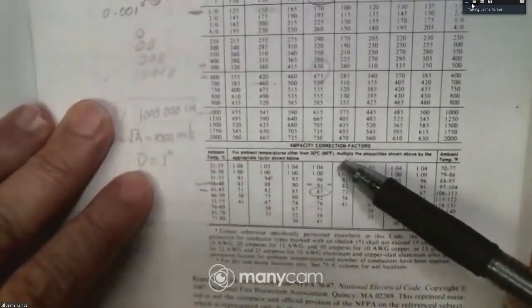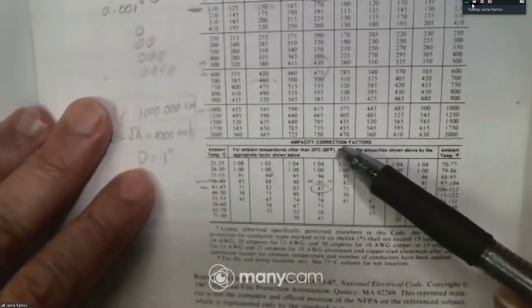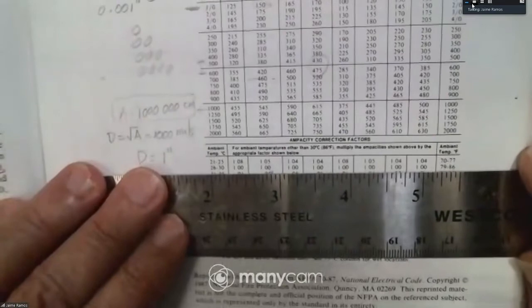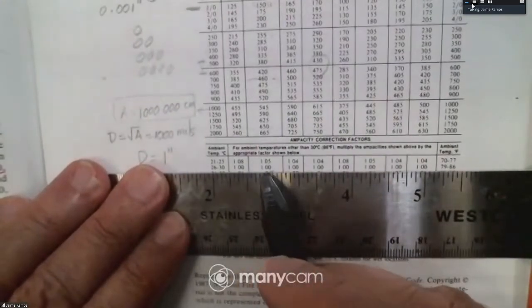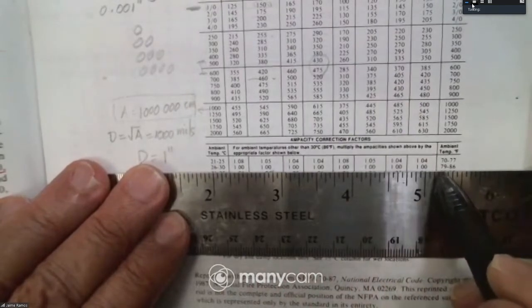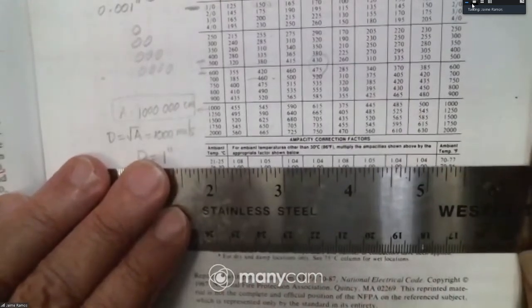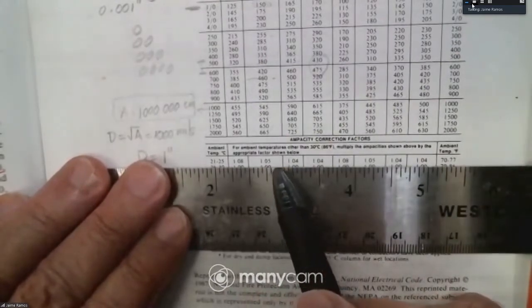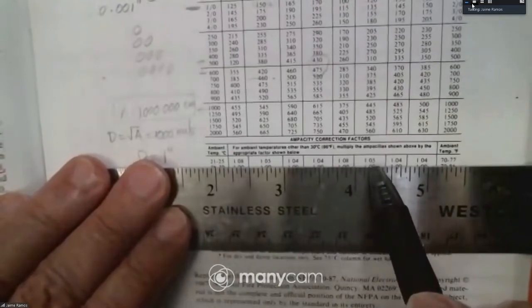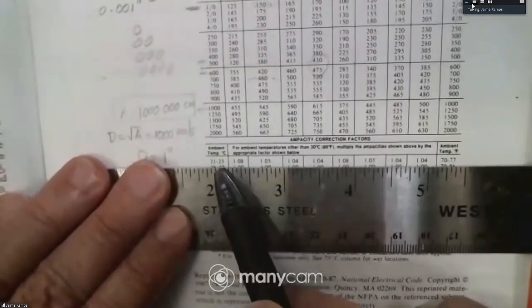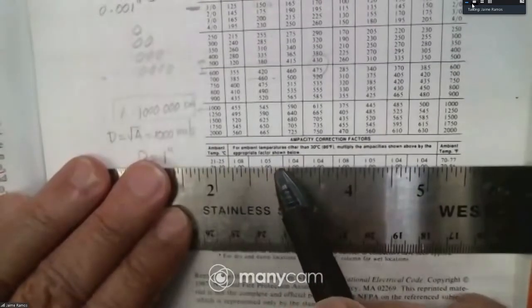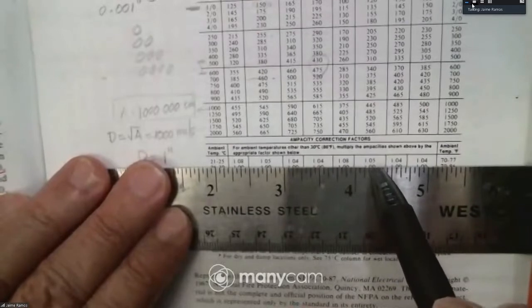Now, if the temperature is different than 30 degrees, there are going to be correction factors. So here is the line for 30 degrees. See this line here? So then on that line, we have correction factor equals unity. Now, if the conductor is cool, for example, inside of freezers or air conditioned rooms where the temperature is less than 30 centigrade, then the ampacity can increase by those correction factors.